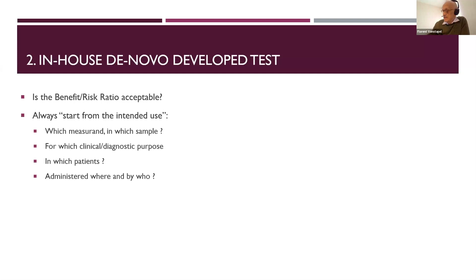And this you can translate in a failure mode effect analysis. You can translate the intended use in sources of risk and impact of failures. And the first question you ask here is, you compare it with the Annex 8 risk classification, because that is a classification which is used in the Article 5.5, and it also immediately relates to the impact of failures. Then you look at analytical aspects. Is the measurement well defined? Is it stable? Then you do an analytical performance validation, which, as I already mentioned, actually is linked to the clinical performance. Clinical performance is going to be your acceptance criterion. So does analytical performance guarantee clinical performance?